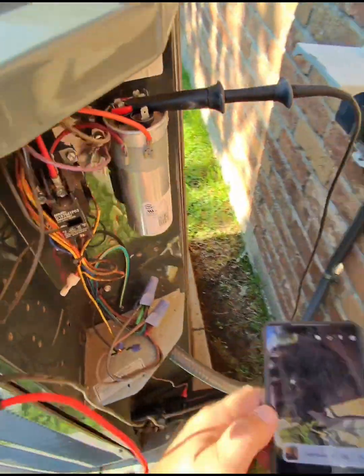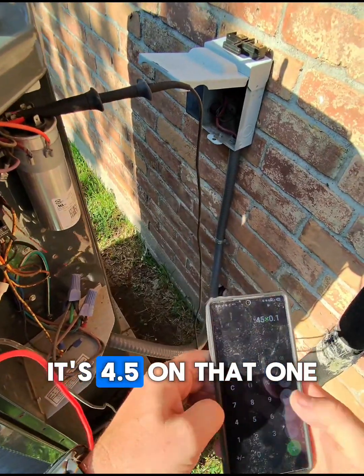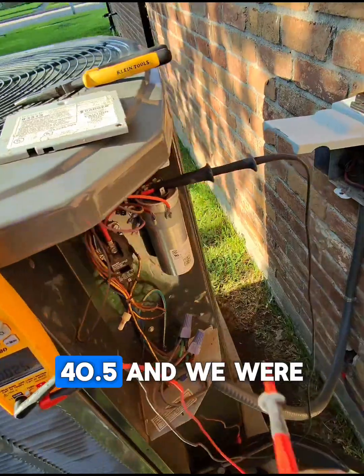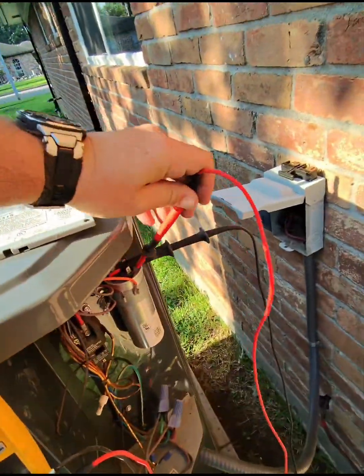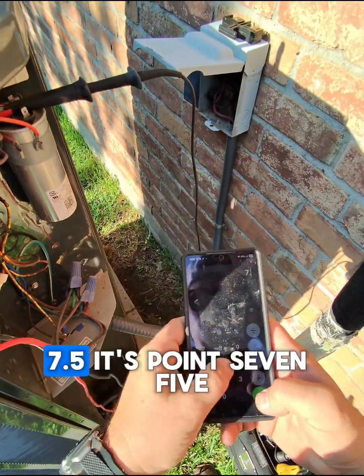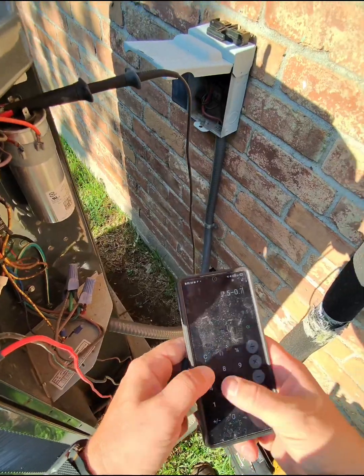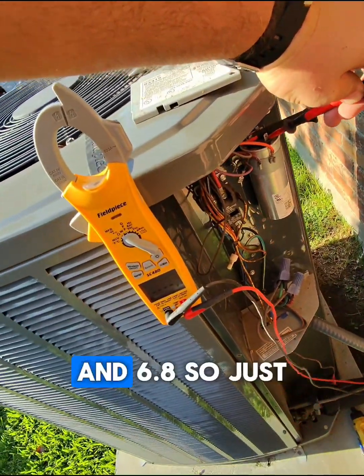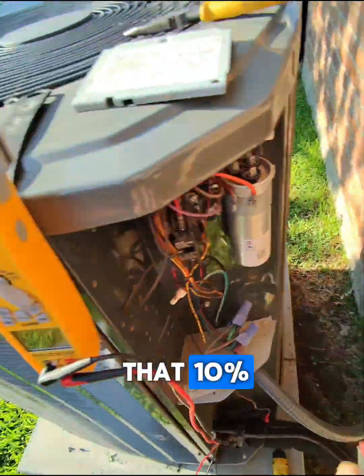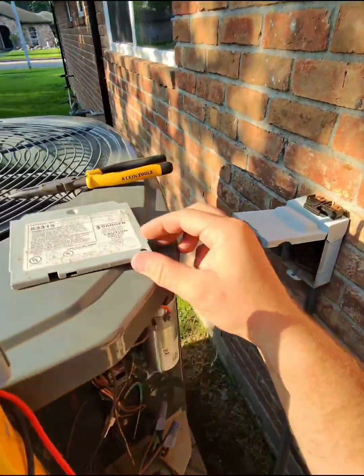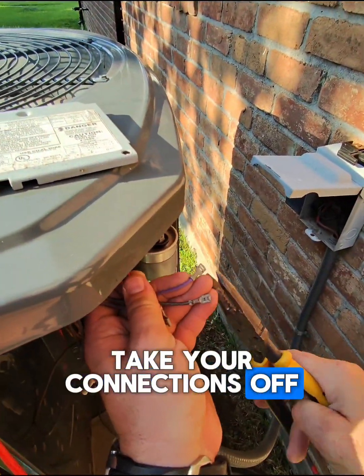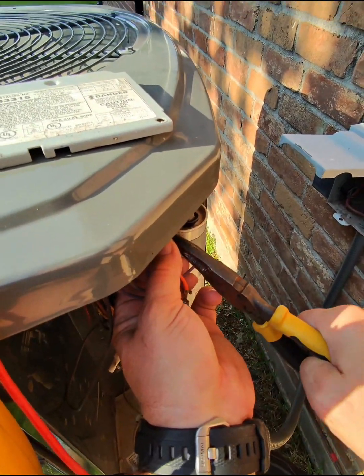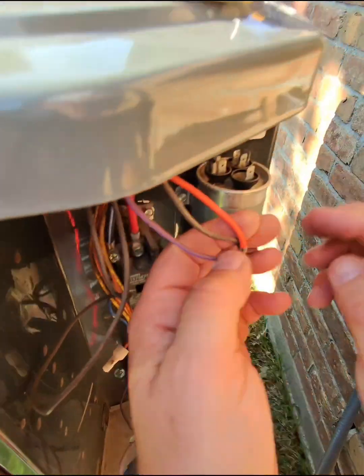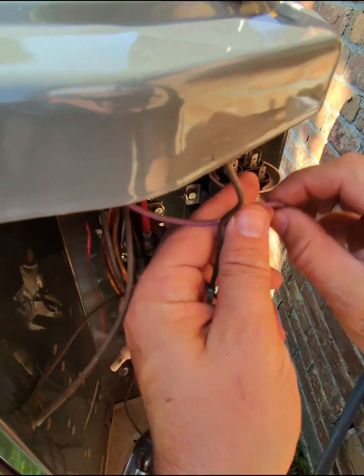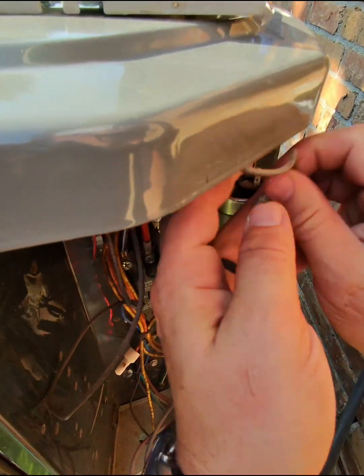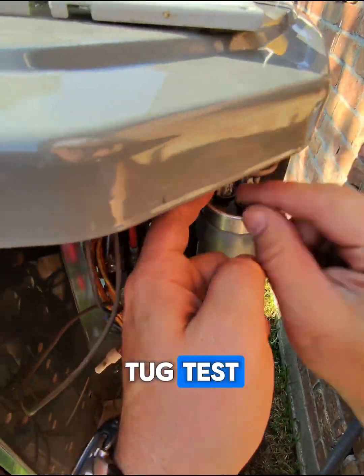So we've got a tolerance of 10%. It's 40.5 on that one, 40.5, and we were at 40.9, barely. And then 6.8 on there, 7.5, 6.75, 6.75, and 6.8. So just barely within tolerance on that 10%. Once again, anytime you take your connections off, inspect them, give them a little tighten. Tug test. Good.